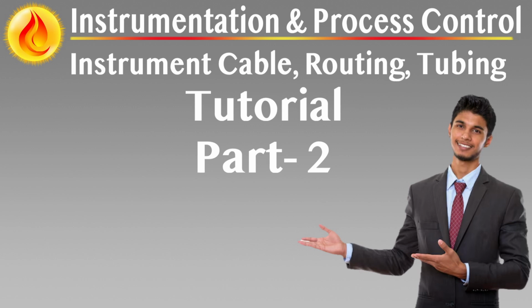All pulling, clamping, and routing operations must comply with the cable manufacturer's specifications regarding bending radius, allowable tension, and sidewall pressure. Noncompliance can lead to insulation breach, conductor deformation, or long-term performance degradation.